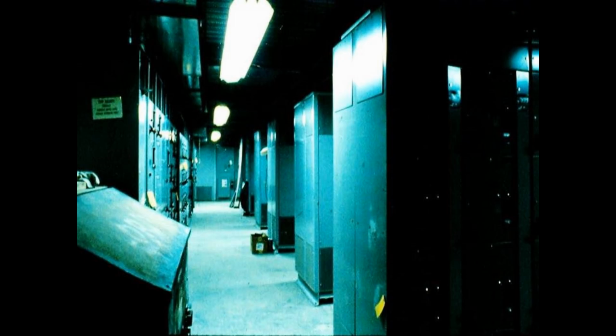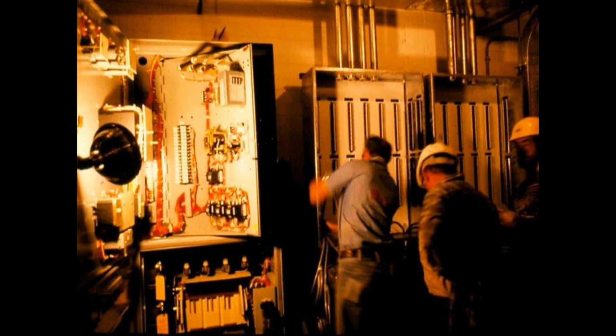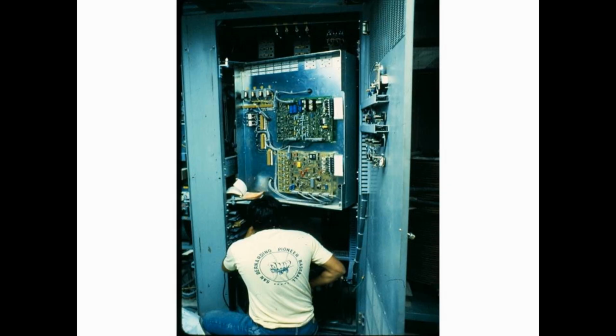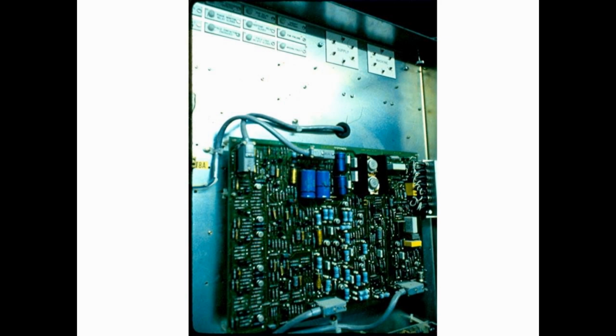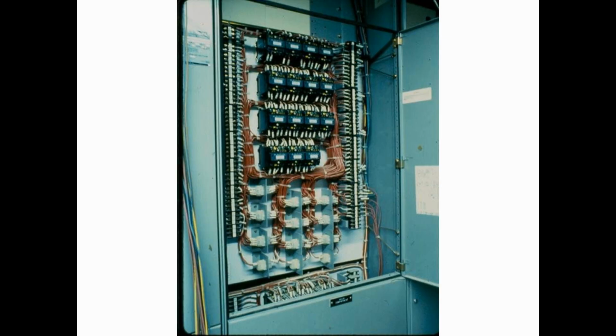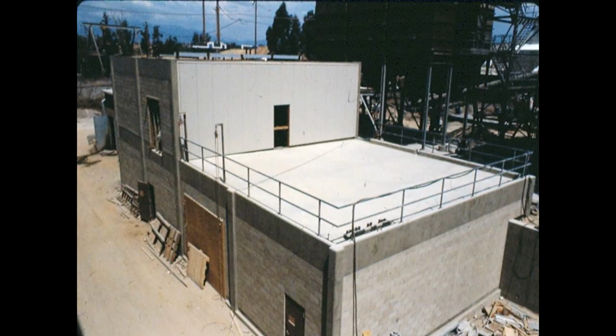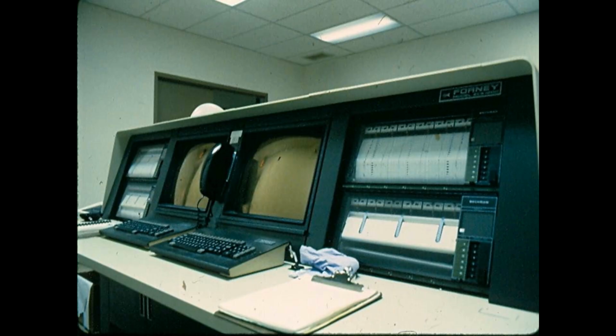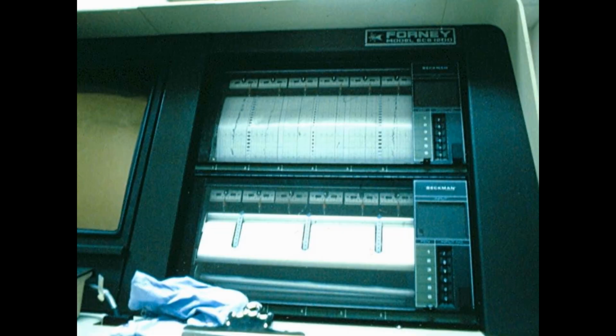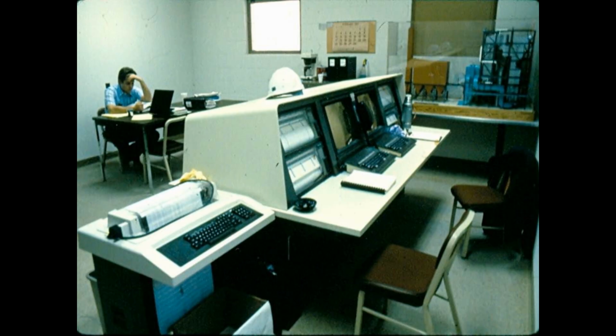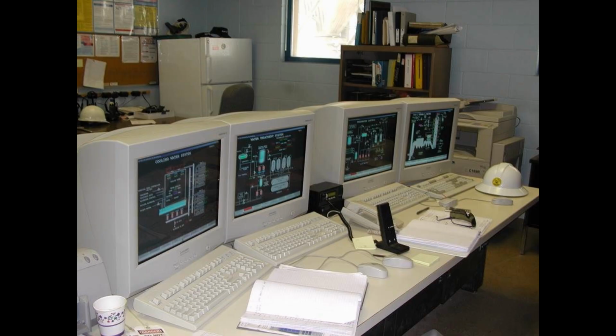A new 12 kV plant load center was installed to accommodate the difficult task of interfacing the new turbine generators, cement plant, and utility. Switchgear installed at the load center permits control of load flow and distribution, and is the focal point for synchronization of the turbine generators. The new cogeneration plant is controlled and monitored through a microprocessor-based distributed control system, which is located in a new cogeneration plant control room. The MBDCS is capable of full process and instrument analog control, generating of alarms and historical data, and ladder diagram type digital control.